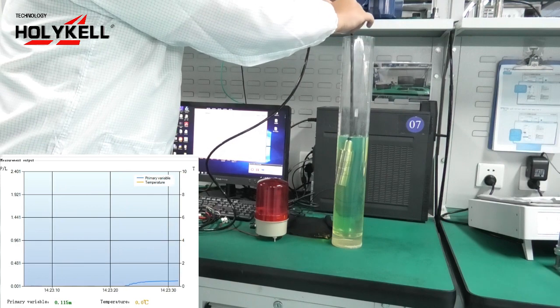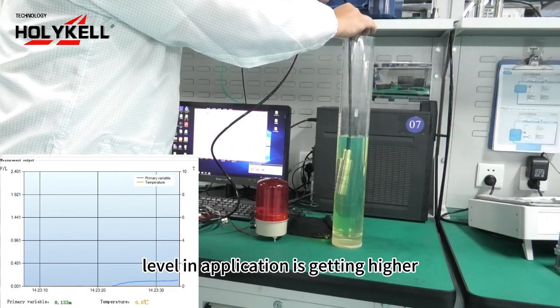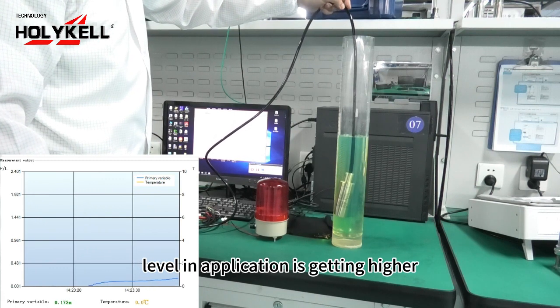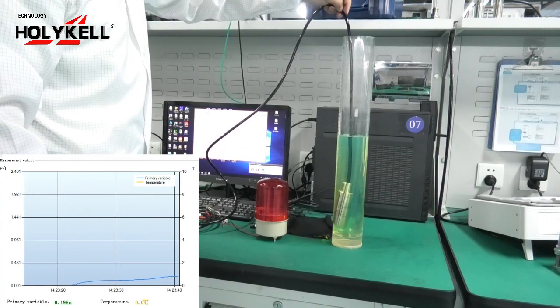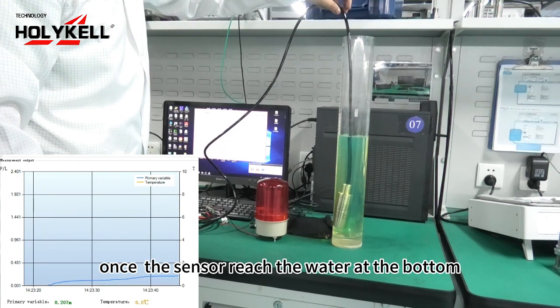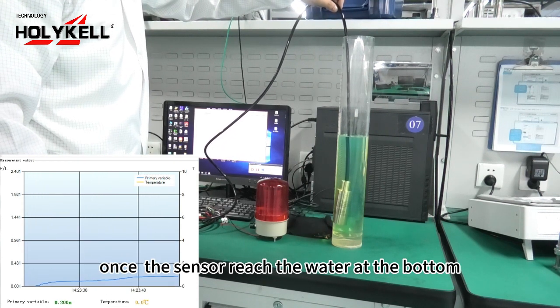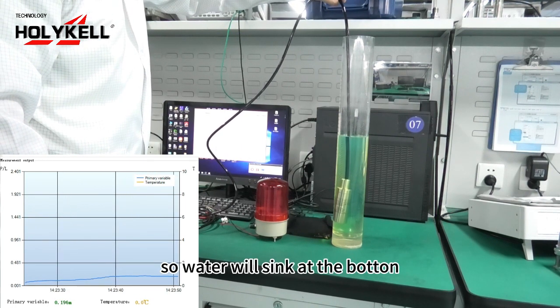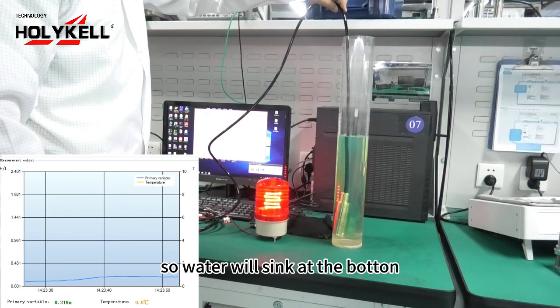As you can see, the level increases in the application. Once the sensor reaches the water at the bottom - because water is much heavier than oil, it sinks to the bottom - the alarm goes off detecting the water.